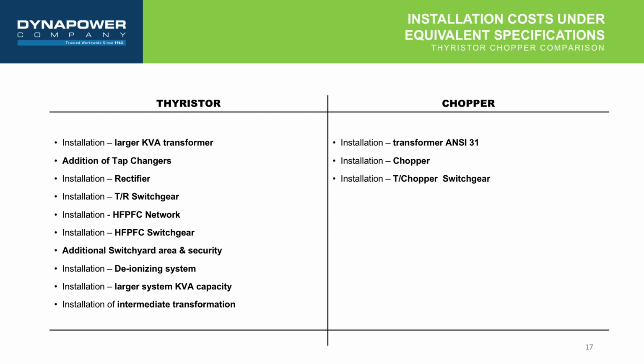For a Thyristor rectifier, there is the requirement for an installation of a larger kVA transformer, the addition of tap changers, the installation of the rectifier, installation of T/R switchgear, installation of HF-PFC network, installation of HF-PFC switchgear, additional switchyard area and security, installation of a deionizing system, installation of a larger system kVA capacity, installation of interface transformers.